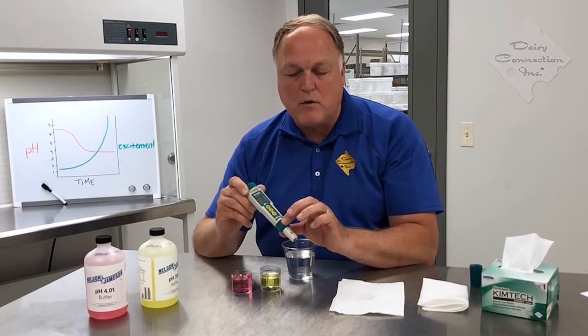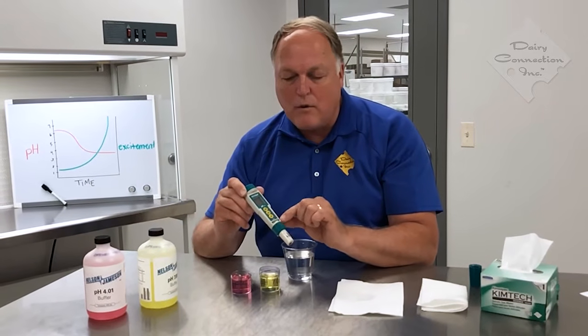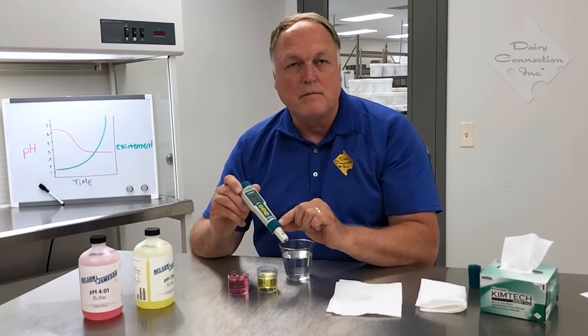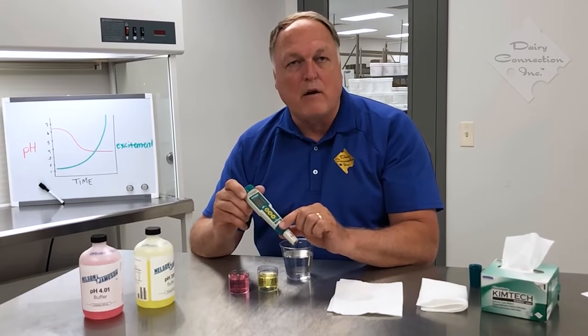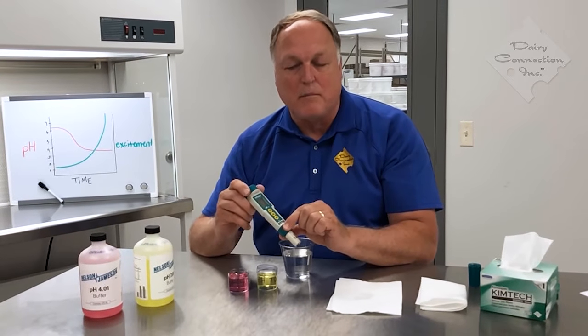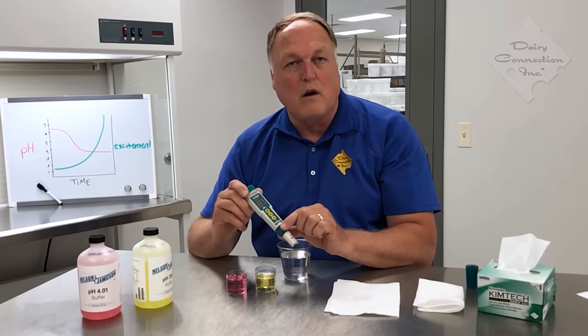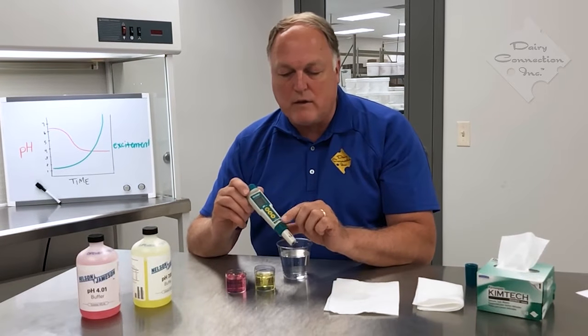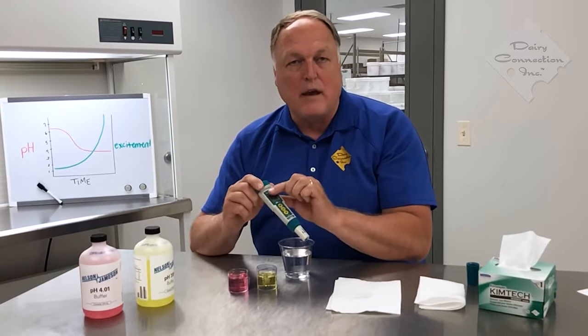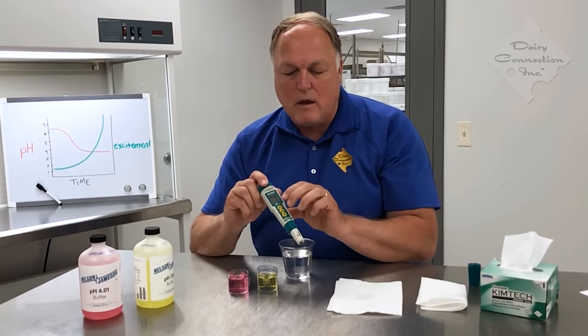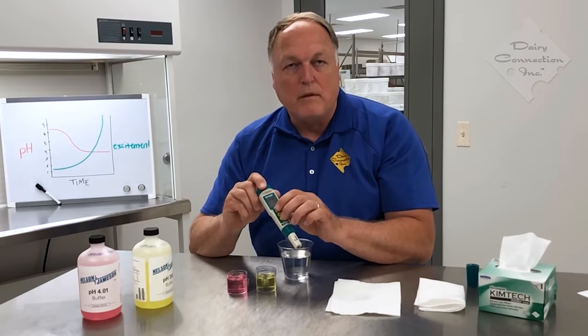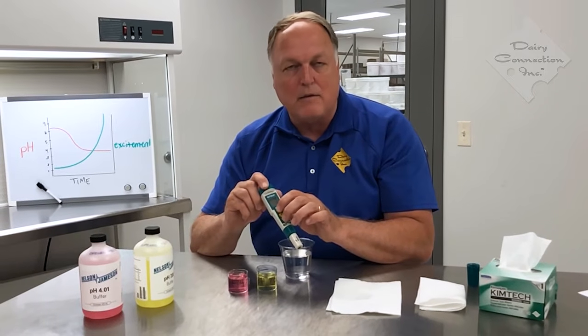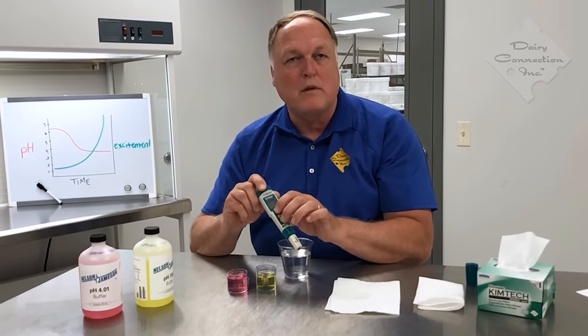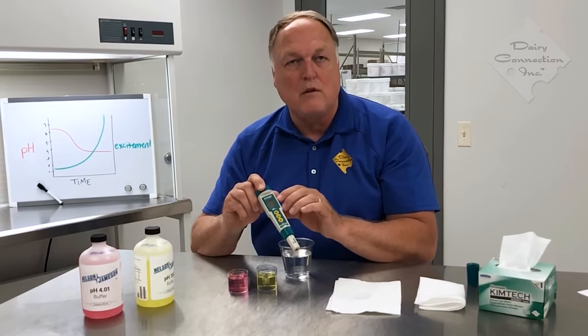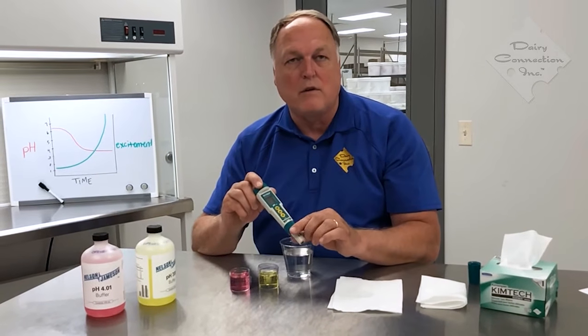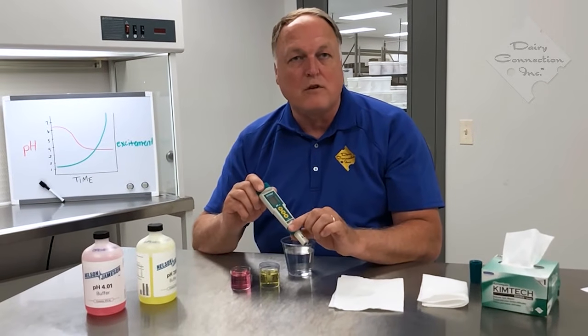The electrode, you should expect a 1 to 2 year life out of it when you purchase this. And again, you can remove the electrode and replace it with a new one without having to replace the entire thing. When you run into some errors, you can get static charges build up. And the recommendation is to do a hard reset. Part of that hard reset process is to take off the cap, remove the batteries, and hold down the top two buttons, the bottom and the top button, at the same time, and that will release any static charge that is built up in your electrode. And then go ahead and reinsert the batteries, and it should function normally after that.